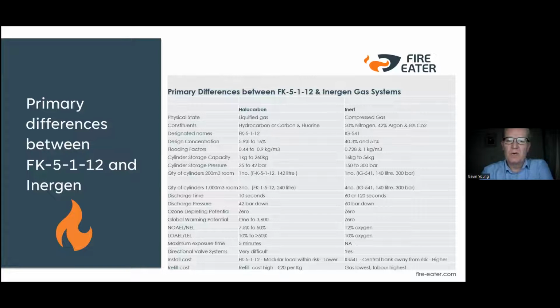The design concentration is between 5.9 and 16% for Novec, and 40 to 51% for Inergen. So there's a lot more Inergen required when it's discharged into a risk or a room to extinguish a fire. There's a lot, which means there's a lot more cylinders and a lot more hardware. So there's a lot less hardware for Novec.